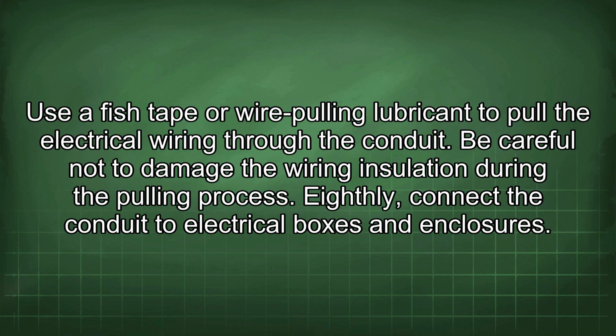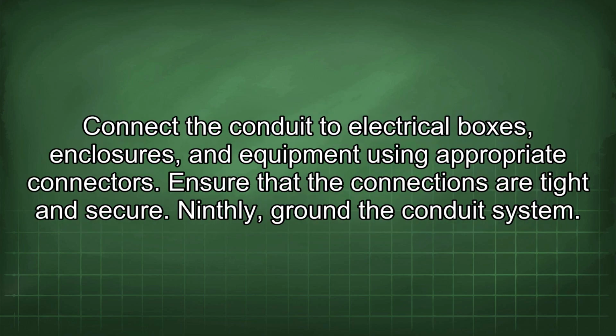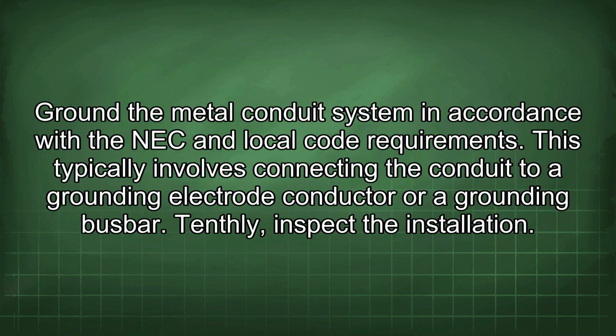Eighthly, connect the conduit to electrical boxes and enclosures. Connect the conduit to electrical boxes, enclosures, and equipment using appropriate connectors. Ensure that the connections are tight and secure. Ninthly, ground the conduit system. Ground the metal conduit system in accordance with the NEC and local code requirements. This typically involves connecting the conduit to a grounding electrode conductor or a grounding busbar.